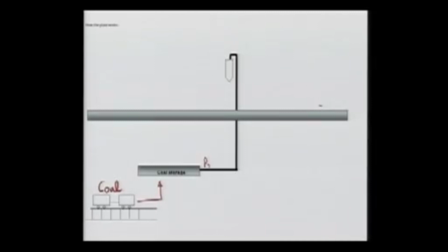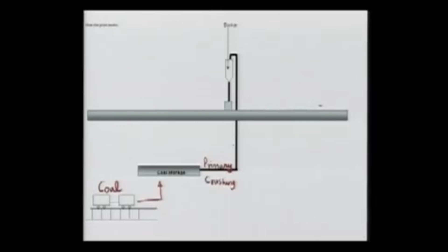that will take the primarily crushed coal to what we call a bunker, or a storage of the coal. Then from the storage of coal we further take it to what we call the coal mill, because now we want to make the coal still finer. And how do we make the coal finer? We take it to the ball mill or the coal mill, and essentially most of the time it is a ball mill. You use huge steel balls and put them into a large container, and the whole thing is rotated, and the balls keep on falling onto the coal, and in the process the coal becomes very fine. So once the coal is fine, almost of the size of, let's say, anywhere between 20 to 100 micron.